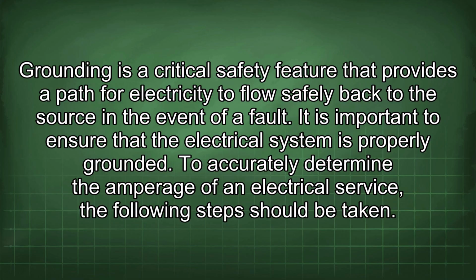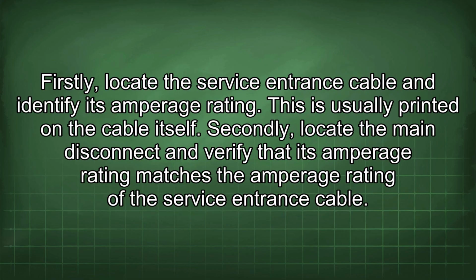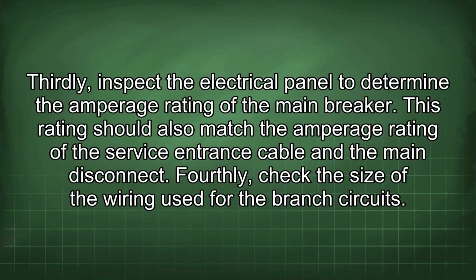To accurately determine the amperage of an electrical service, the following steps should be taken. Firstly, locate the service entrance cable and identify its amperage rating. This is usually printed on the cable itself. Secondly, locate the main disconnect and verify that its amperage rating matches the amperage rating of the service entrance cable. Thirdly, inspect the electrical panel to determine the amperage rating of the main breaker. This rating should also match the amperage rating of the service entrance cable and the main disconnect.